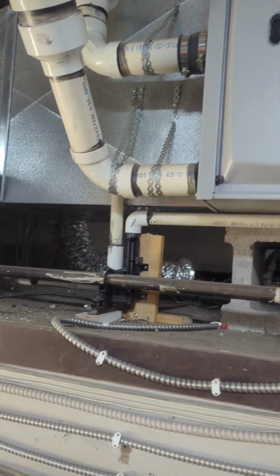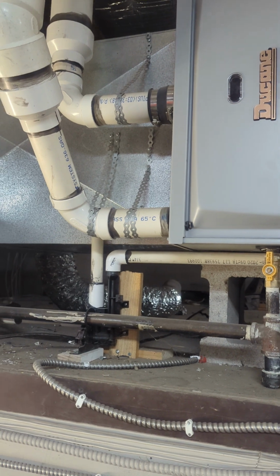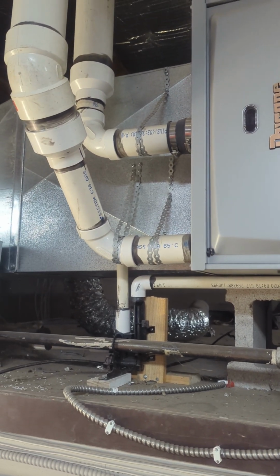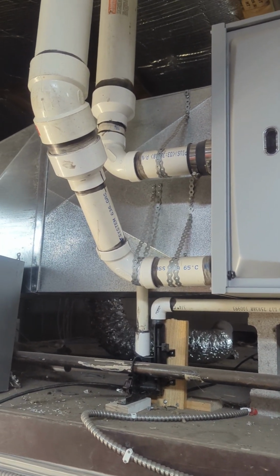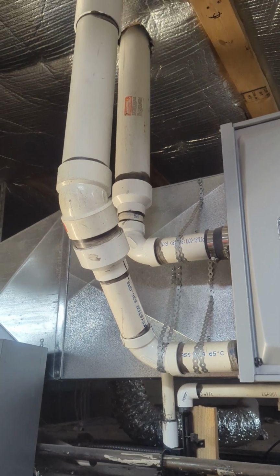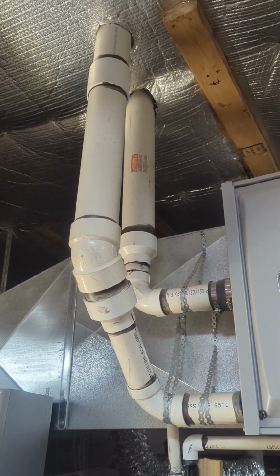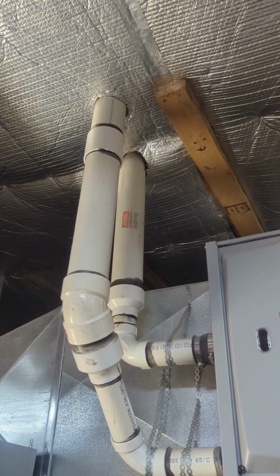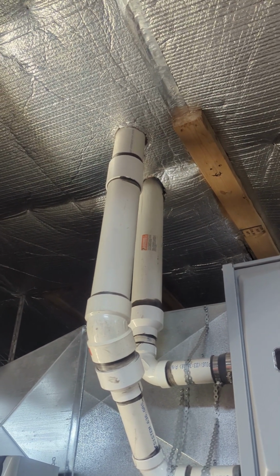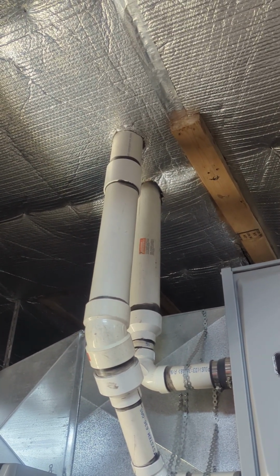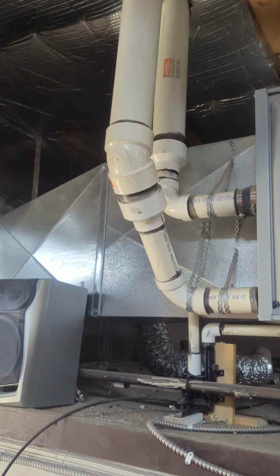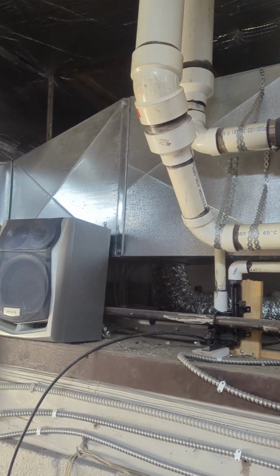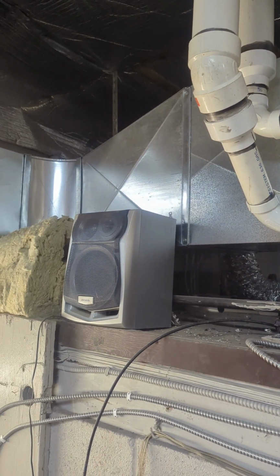But there's the venting. So it starts off as 2-inch. And with a 90,000, you start it off with 2-inch and then you increase to 3. So it increases to 3-inch venting all the way through the roof. And you can't see above that, but it does a 90 and goes out a horizontal wall as well. So since this is just for a shop, we didn't have to get too fancy. It just had to work.